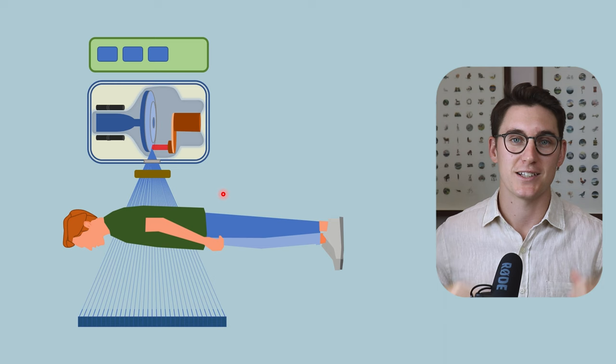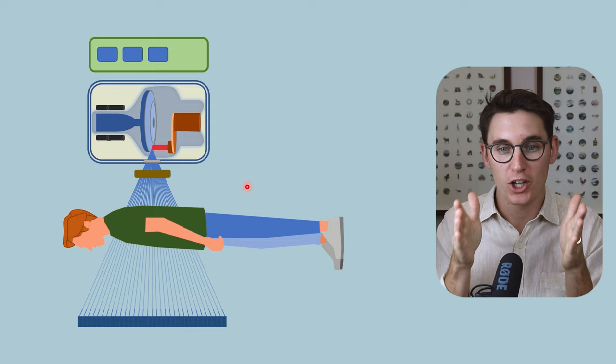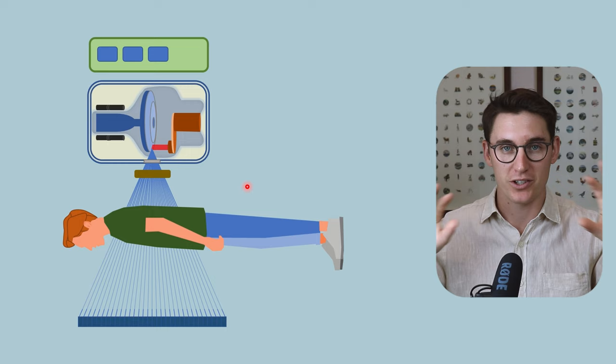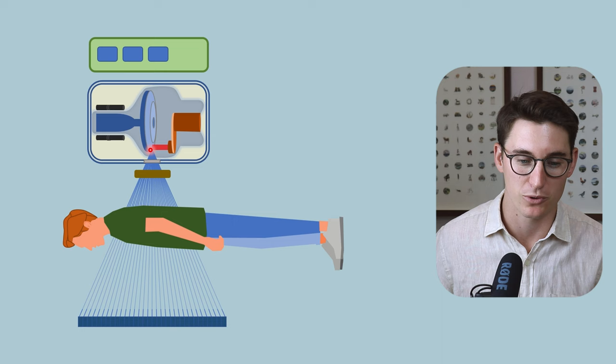The second thing that we can do to these X-rays leaving the X-ray tube is collimation. We can narrow down that X-ray beam to a specific area on our patient, an area that we want to image without exposing other areas of the patient to X-ray radiation. The X-rays will come off of our anode in very specific geometric orientations, and this is what's known as the line focus principle, which we will spend a whole talk going over.